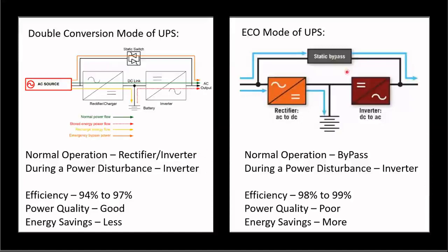While here, these things are generally not used the way they are used here. So less cooling is required, and we also save on the energy side. So that's the main difference. Also, one thing is the transfer time. If something goes wrong, say utility power goes off here, the transfer time will be less because the inverter is already energized, right? But here that's not the case, because it will take time for the inverter to energize since power is flowing through the static bypass.